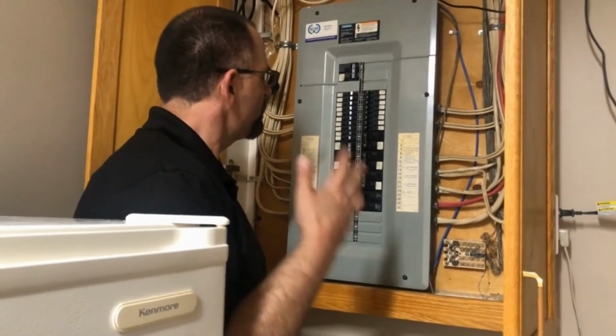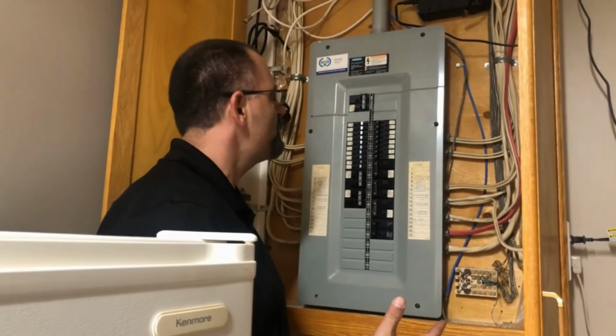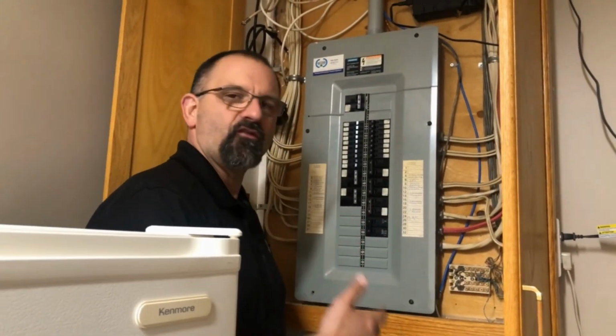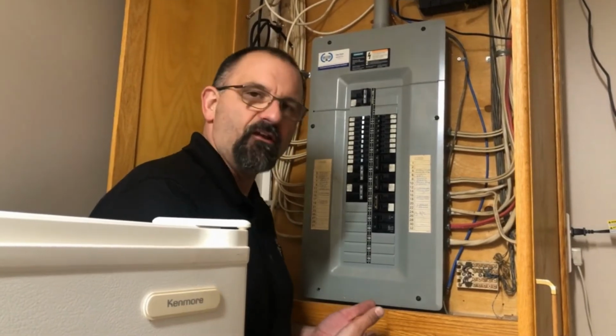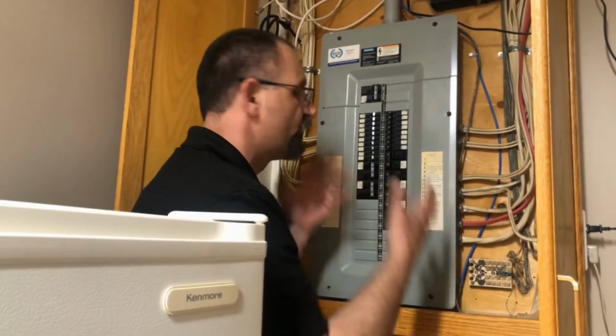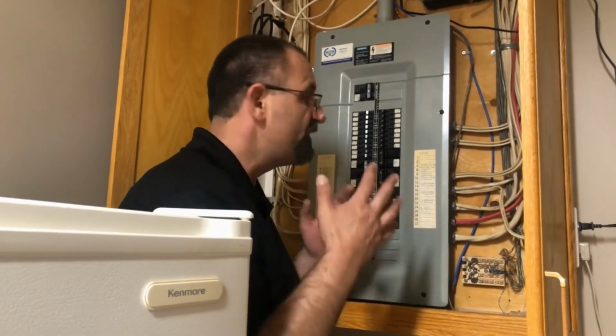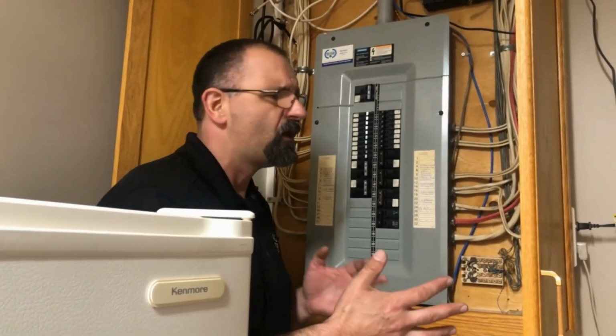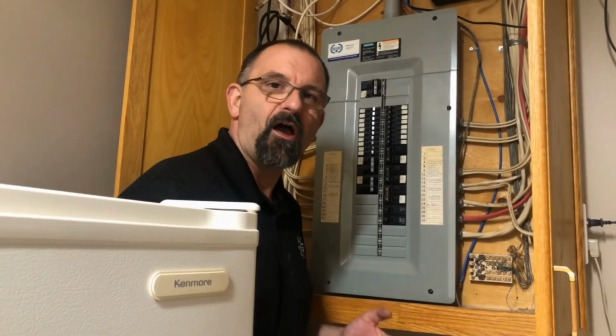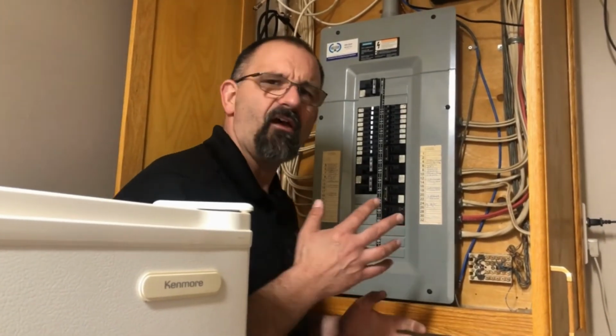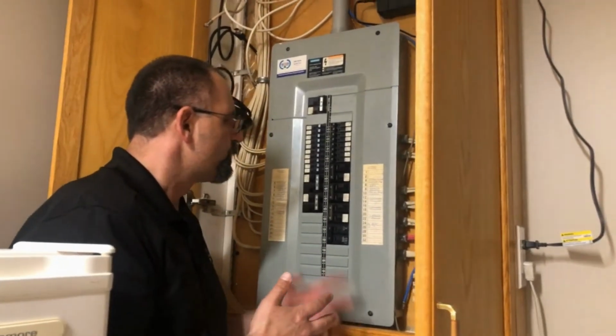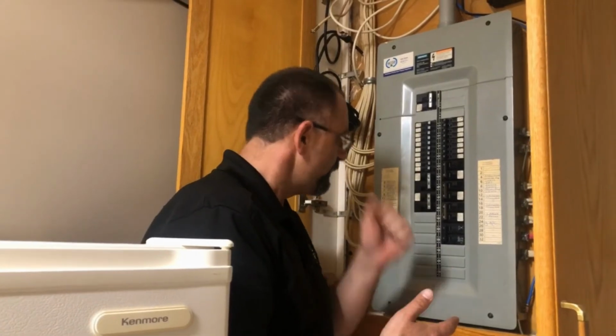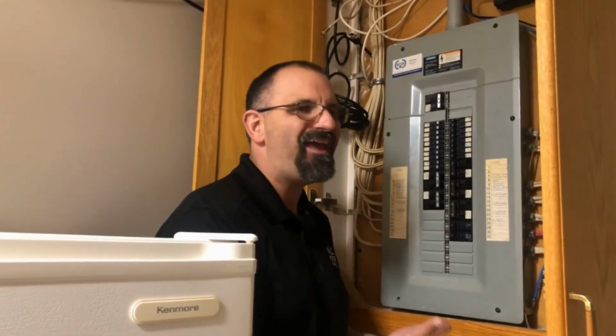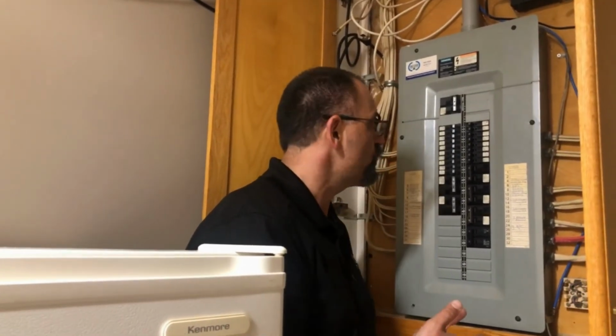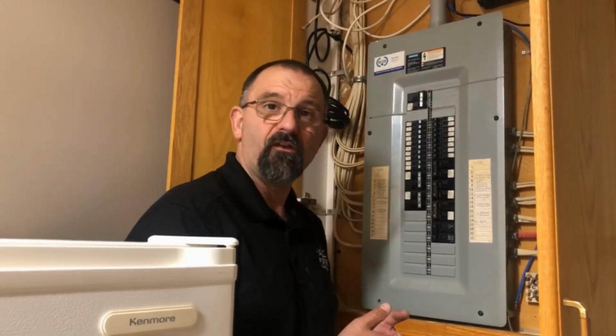All right, so we got our panel cover back on, and this panel's now safe. So if you're buying an older home, you want to keep in mind that the electrical panel is no different than your roof, your hot water tank, your furnace. Even though there's no moving parts in here, there's a lot going on in this electrical panel, and things wear down, things break down, and ultimately, especially with the older panels, those of you that have heard my rants and raves before about the Federal Pioneer and Federal Pacific panels, those panels have all sorts of problems, mainly breakers that don't trip when they're overloaded. So if you're going into a home that has an older electrical panel, Commander is another brand, Federal Pioneer for sure, you really want to be aware that it's time to replace that panel.